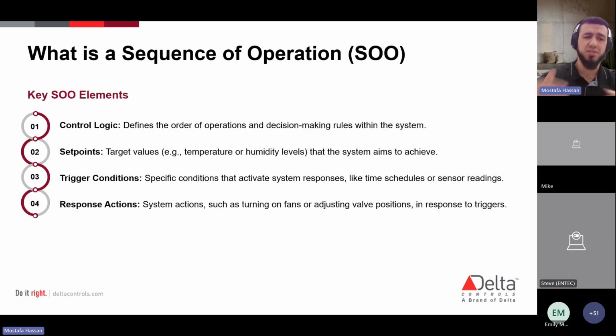Then you have trigger conditions. So a lot of these are interrelated, but you don't really have to follow the sequence this way, but it's good to know that these make up every line in your sequence of operation. There has to be a reason you're trying to control a certain piece of equipment or a certain field device, right? And then your response action is things like opening a valve, toggling the thermostat, turning on the light, turning off the light, things like that.